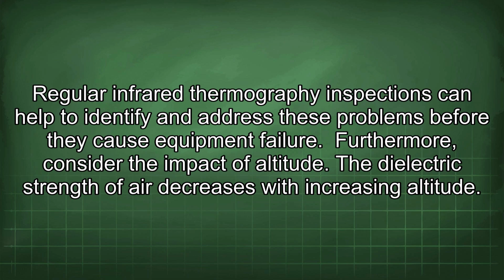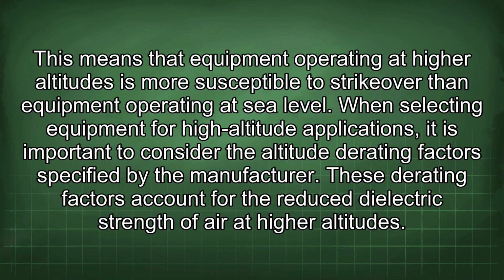Furthermore, consider the impact of altitude. The dielectric strength of air decreases with increasing altitude. This means that equipment operating at higher altitudes is more susceptible to strikeover than equipment operating at sea level. When selecting equipment for high-altitude applications, it is important to consider the altitude derating factors specified by the manufacturer. These derating factors account for the reduced dielectric strength of air at higher altitudes.